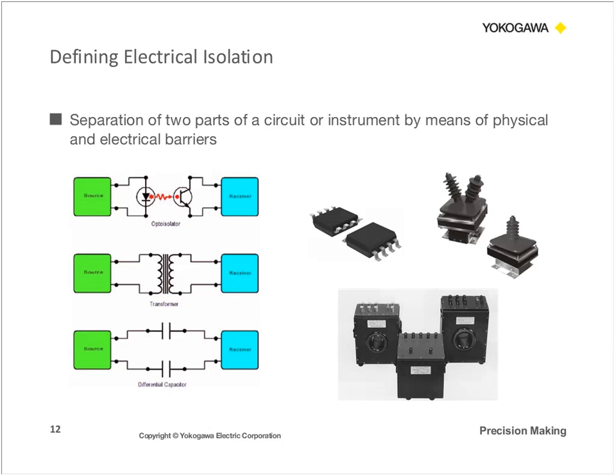So isolation can really mitigate a lot of the problems that we just talked about and presented at the beginning of this slide, which were ground loops, unwanted noise, and risk of electric potential. There are a number of specific isolation devices that you can implement, both into your internal system design as well as external isolation devices, to really mitigate these problems. And as you can see there on the left, I've given you some examples where your source is physically and electrically isolated from the receiver.